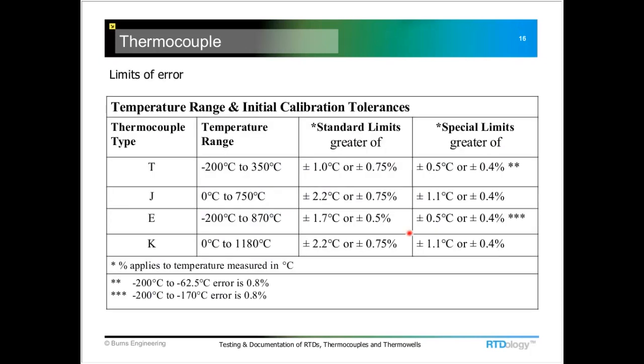And those are actually the base thermocouples. You can see here, like the type T and the type E are the more accurate of the four basic types of thermocouples. And so again, that verification document will just say, yes, it's the type T, and it's special limits of error, for example. And a test, I know we do it at 100 degrees C just because it's a real convenient point. You may see other temperature points used. And now there are some thermocouple standards, and they will be tested at several different temperatures, and you'll get a little different kind of document with that, a calibration certificate, much like what we looked at previously.